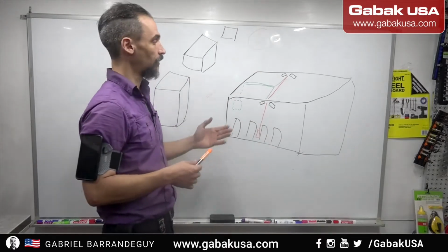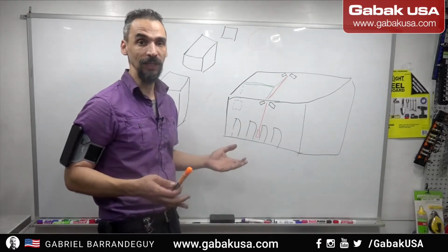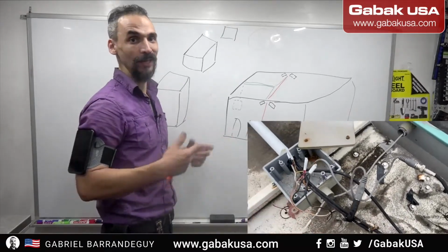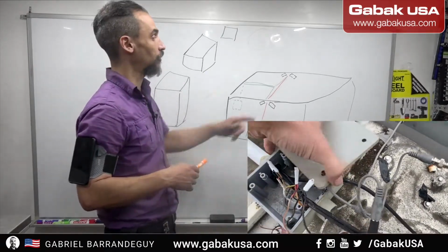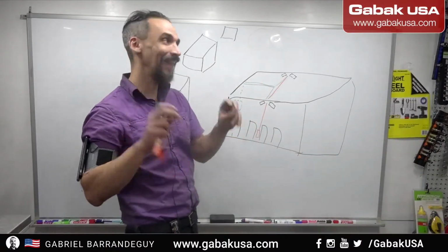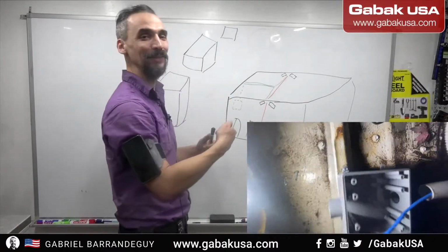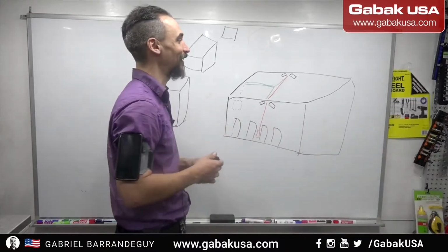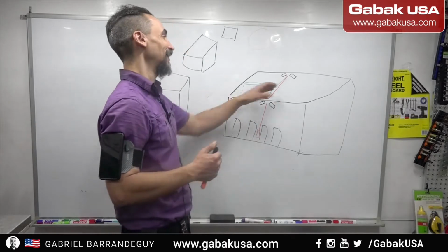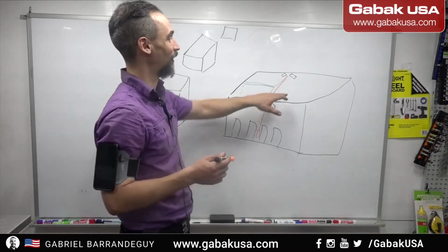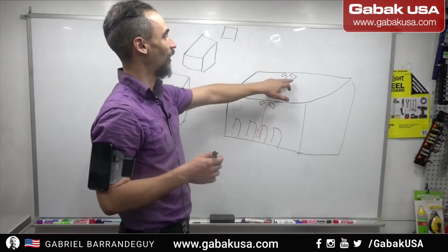So basically the problem that they had: because everything was exposed, the weather will damage any cable, any connection, and everything. Also the junction box that they had, they made a hole on the side. Things were not sealed properly. It was kind of a disaster. So you're also going to learn from the mistakes of other technicians. In this case, I had to fix that.